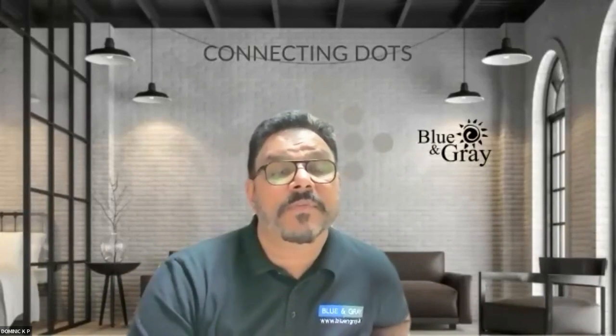Okay, though it is not related to today's subject, Hari Katla is asking, sir, I'm working in a fire and combustion research center. Some of the research equipment is giving a little bit of shock. For the earth pit, what type of earthing mixture should we use? So he's asking for one suggestion, one doubt. My God, your shock has nothing to do with the earth pit. If your shock has something to do with faulty equipment, the insulation must have gone. You should check the insulation resistance of the equipment, and if needed, you have to repair it. Hope Hari Katla, you got the message. Please check the equipment, not the earth.